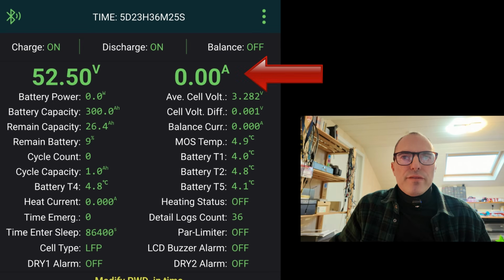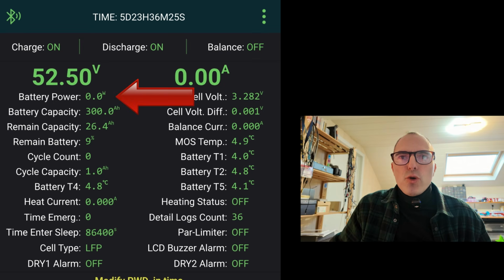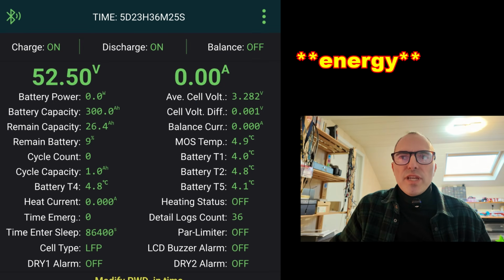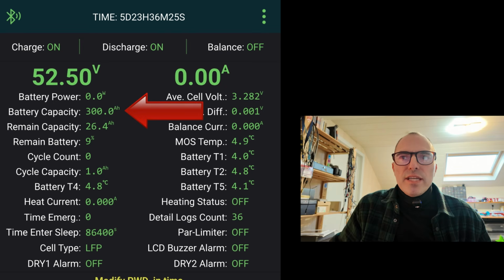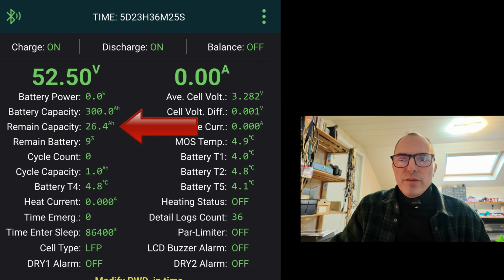Voltage and current speak for themselves. When current flows into the battery, the value becomes negative. Let's go over all the other parameters. Battery power shows the actual power that flows in or out of the battery. The battery capacity is the total capacity of the battery. It's the value you entered previously. Remain capacity is the capacity available in the battery. The battery needs to make at least 1 full cycle to have a correct value.